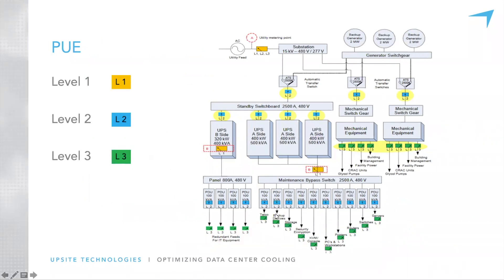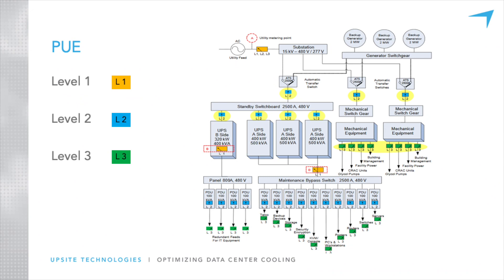This schematic shows where Level 1, Level 2, and Level 3 measurements are taken — the UPS for Level 1, floor PDUs for Level 2, and the actual power strips within the racks for Level 3. Is any one level better than the other? Level 3 gives the most granularity and real-time information. But whatever level you can accurately measure and are comfortable with, doing it at the regular intervals recommended by the Green Grid will not be wrong and will help you gain efficiency in your data center.